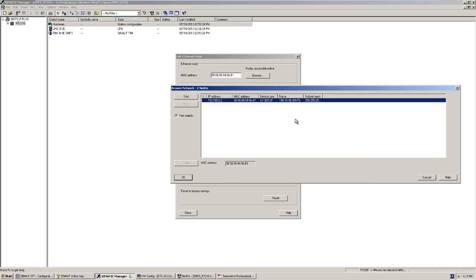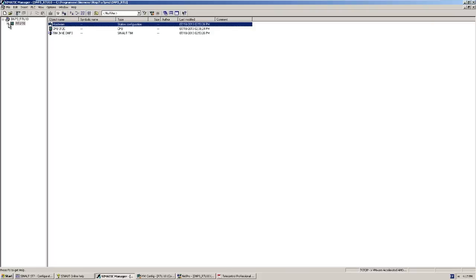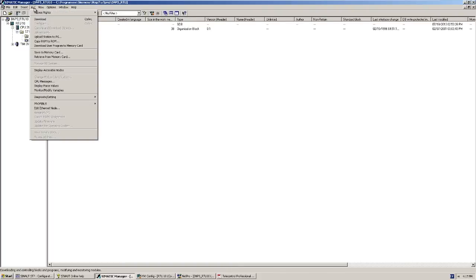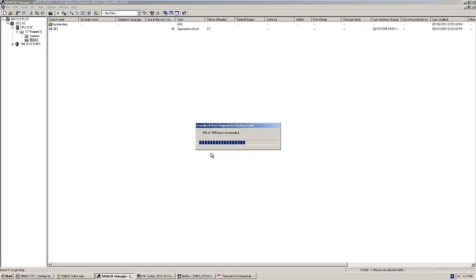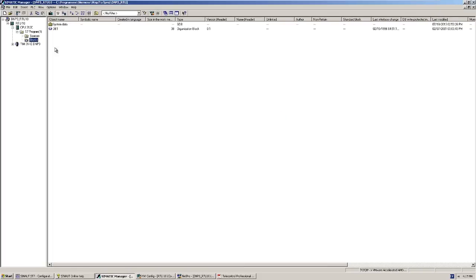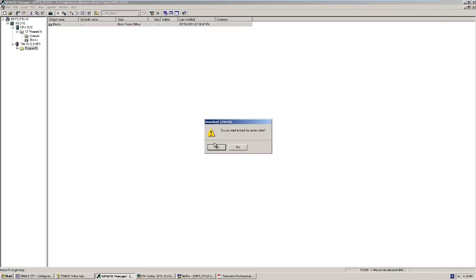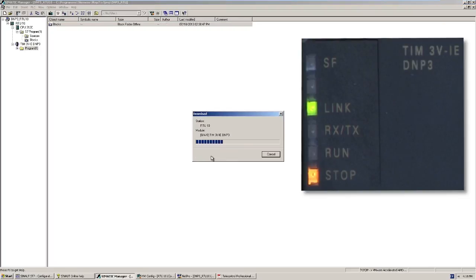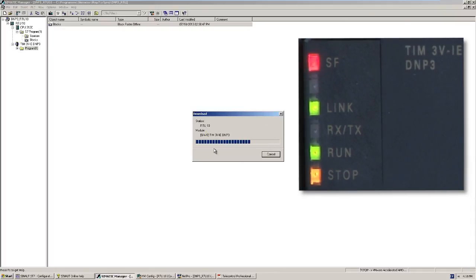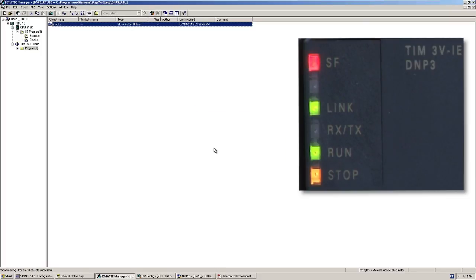For loading the configuration, the programming device is connected with the DNP3 TIM. I assign the IP address to the TIM module using the PST tool. Next, I first load the CPU and then the TIM module.